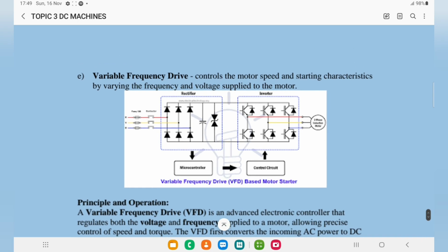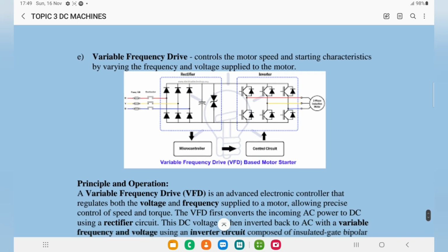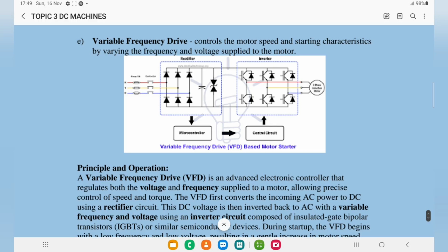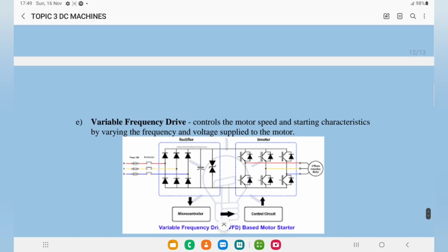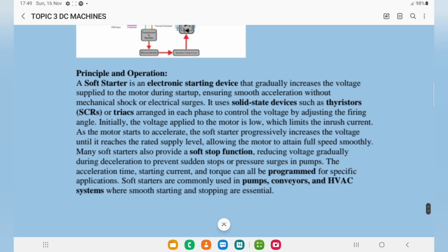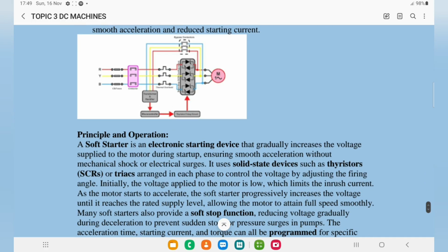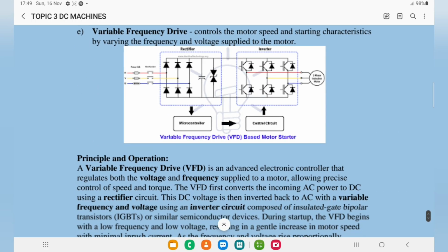Then we come to the final three-phase motor starting method, which is the variable frequency drive. In our syllabus, we mentioned special machines. The soft starter and the variable frequency drive fall under special machines. The variable frequency drive controls the motor speed and starting characteristics by varying the frequency and voltage supplied to the motor. From the name, we are talking about a variation in frequency and voltage.